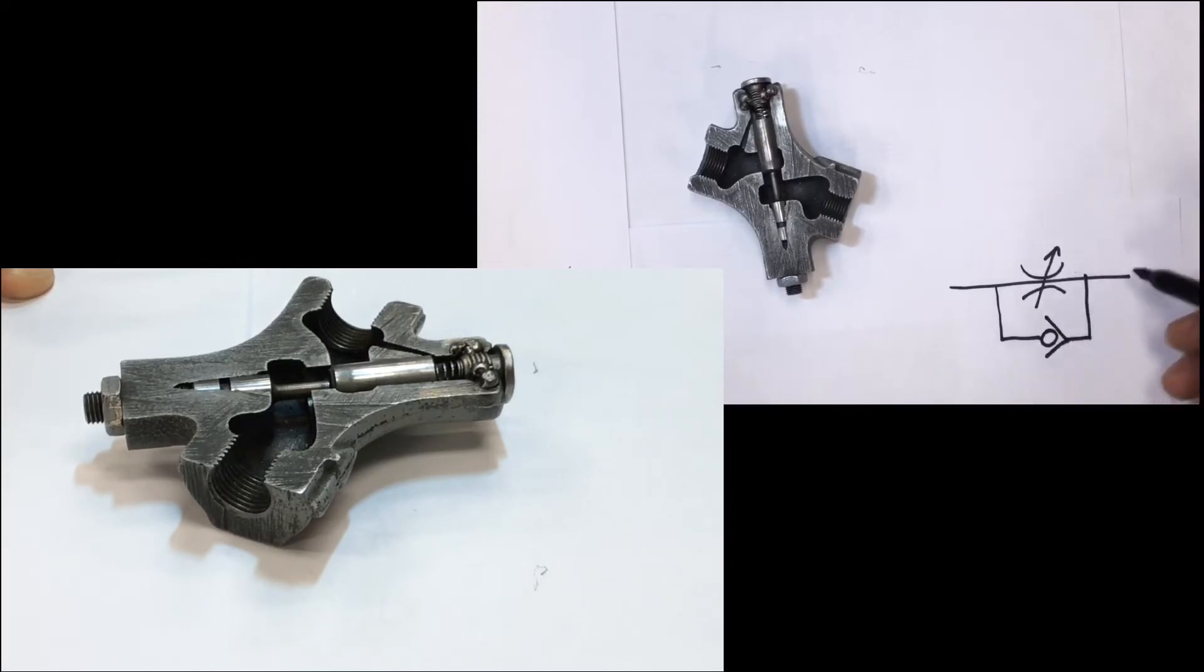Now you can see that when oil is flowing in this direction, it can flow through the orifice and open the check and flow around. So it's free flow in that direction. And then in this direction, when oil is coming back, it's metered flow.